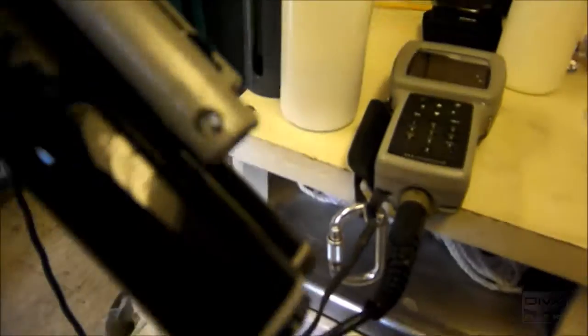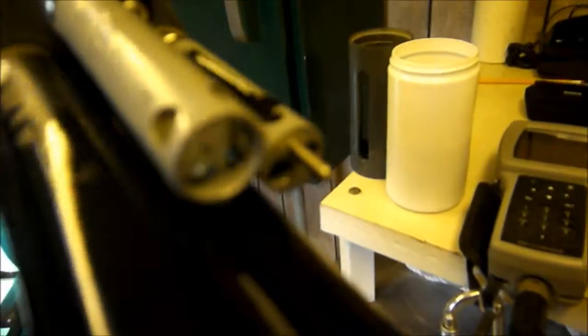One thing you'll want to pay attention to as your probe gets older is this millivolts. Different pH buffers will show different millivolts. So take a look at the instruction manual and make sure it's reading within the proper range. So that is it for pH calibration. The pH electrode is the one with a glass bulb inside of it, pH probe. So you want to make sure that's clean.